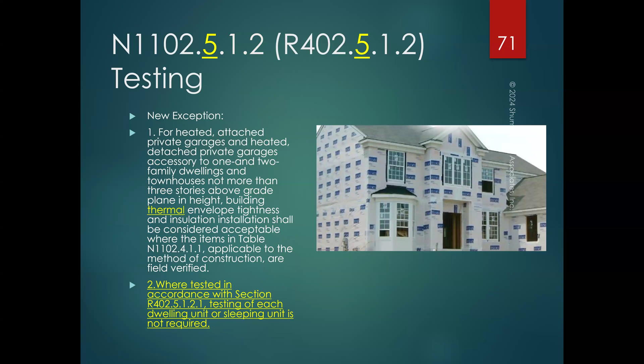R402.5.1.2.1. Not each unit is required. This is where we're talking about unit sampling. If you've got multiple dwelling units or multiple sleeping units, whether it's an R3 boarding house or something else that we could build out of the IRC, six or less for a boarding house. Then if you've got 8 or more dwelling units or sleeping units, 7 or 20% of the dwelling units, whichever is greater, shall be tested. So if you've got 8 units, you've got to test 7 of them. So you get one free. You don't get to take all of them off. If you have 10, then you still have to do 7.